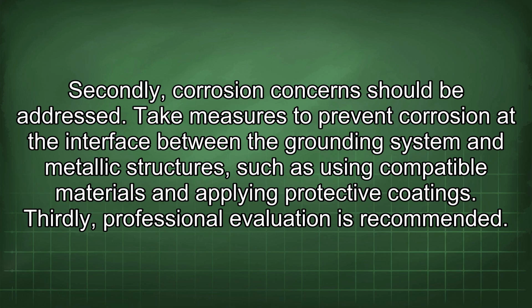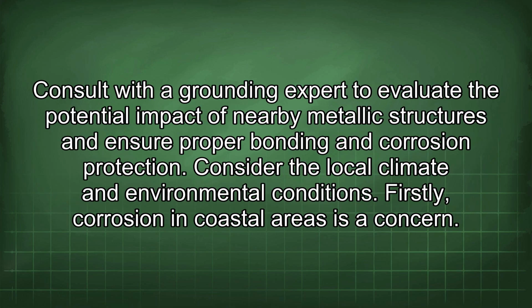Take measures to prevent corrosion at the interface between the grounding system and metallic structures, such as using compatible materials and applying protective coatings. Thirdly, professional evaluation is recommended. Consult with a grounding expert to evaluate the potential impact of nearby metallic structures and ensure proper bonding and corrosion protection. Consider the local climate and environmental conditions.